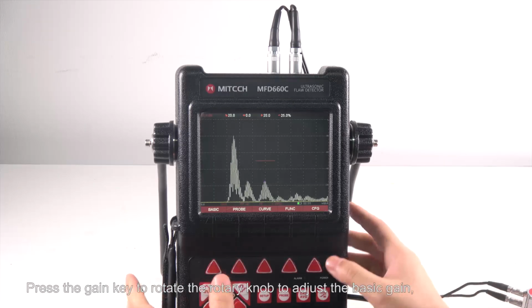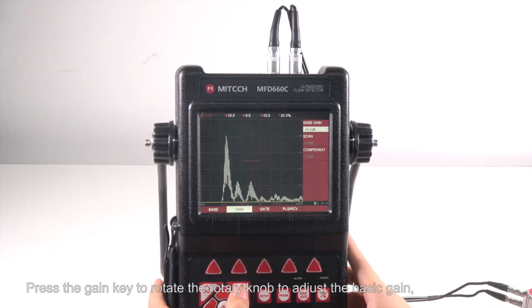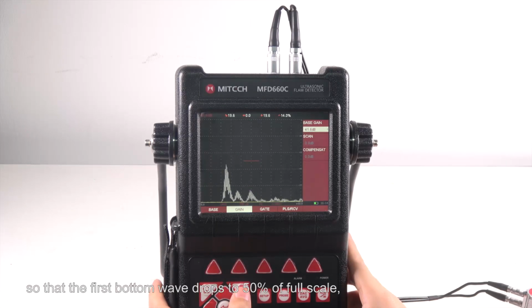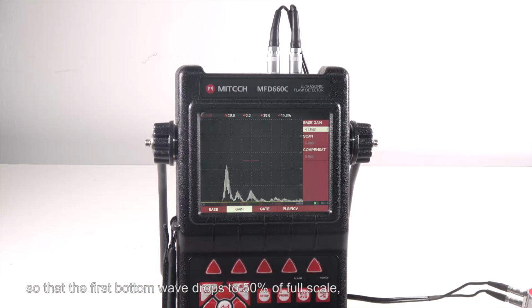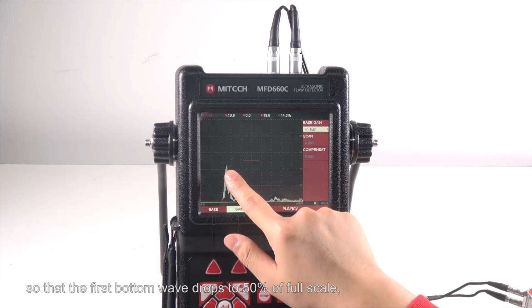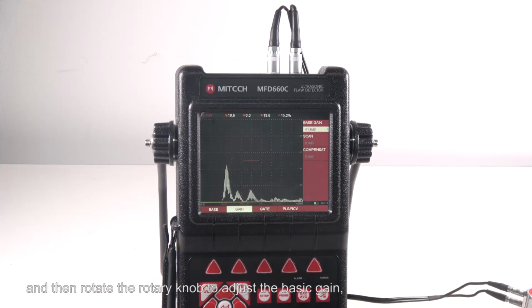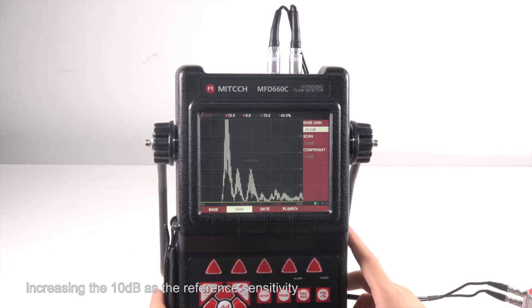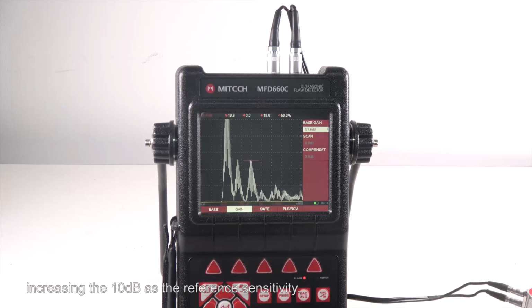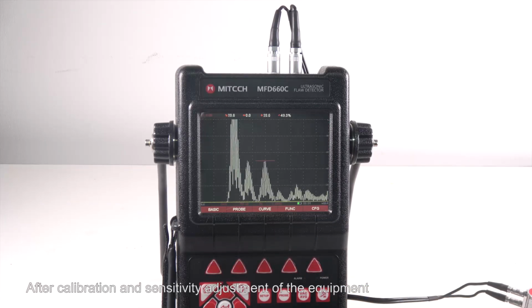Press the gain key and rotate the knob to adjust the basic gain so that the first bottom wave drops to 50% of full scale. Then rotate the knob to adjust the basic gain, increasing it by 10 dB as the reference sensitivity. After calibration and sensitivity adjustment, the equipment can be used for thin plate detection.